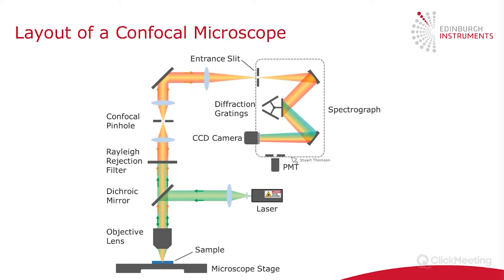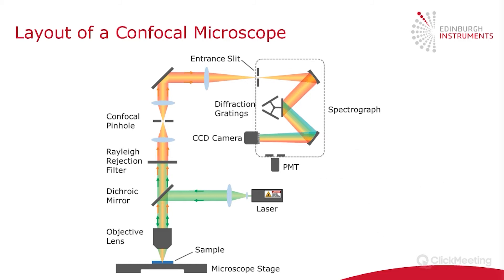There is also a second detector. The RMS 1000 can also function as a photoluminescence lifetime microscope using a single point detector — a photomultiplier tube — to measure photoluminescence lifetimes. Instead of imaging onto the CCD, the light can be directed through a slit and onto the PMT for lifetime measurements. I hope that gives a brief overview of how these instruments work, as I'll be referring to the various parts throughout the rest of the talk.